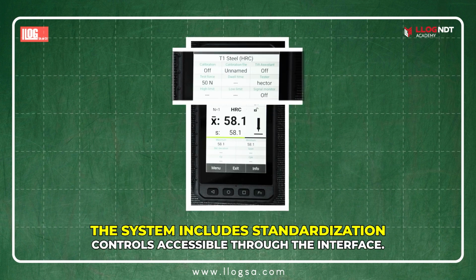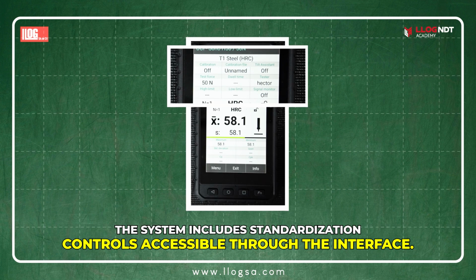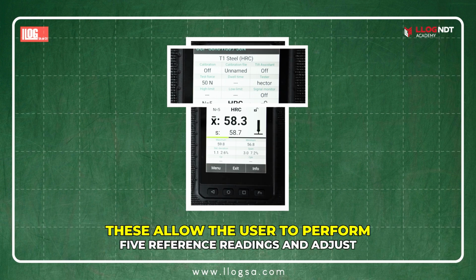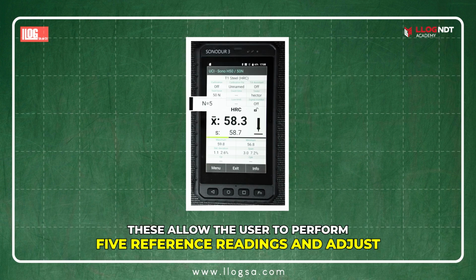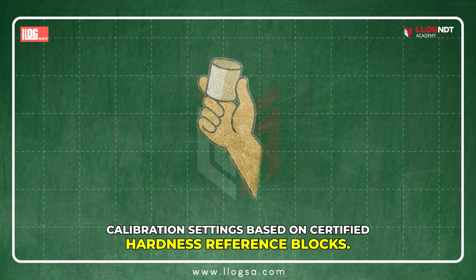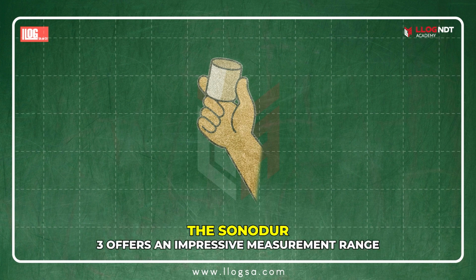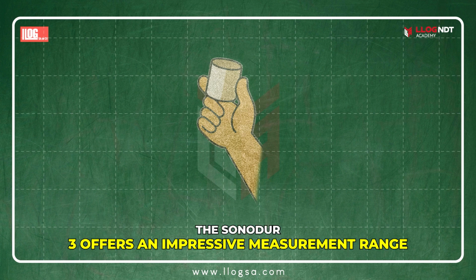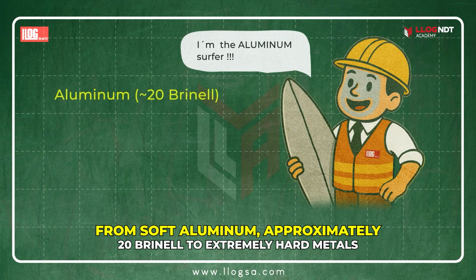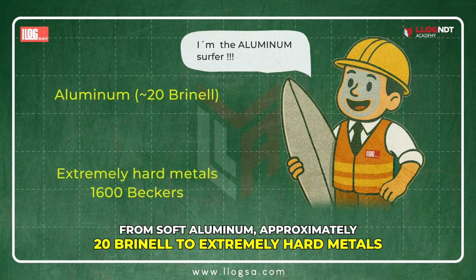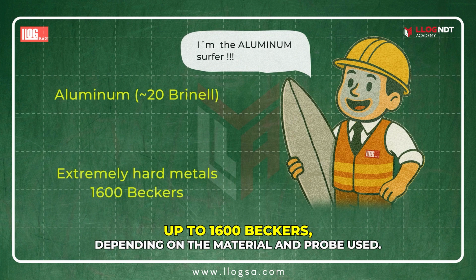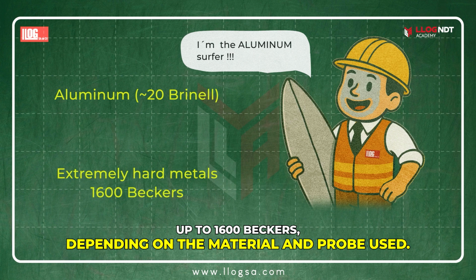The system includes standardization controls accessible through the interface. These allow the user to perform 5 reference readings and adjust calibration settings based on certified hardness reference blocks. The Sonodur 3 offers an impressive measurement range, from soft aluminum, approximately 20 Brinell, to extremely hard metals, up to 1600 Vickers, depending on the material and probe used.